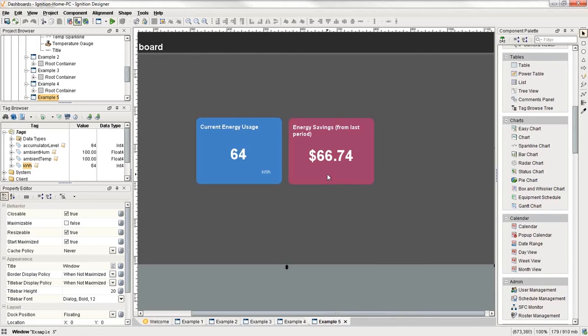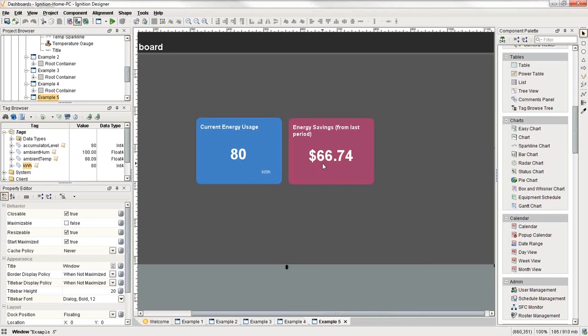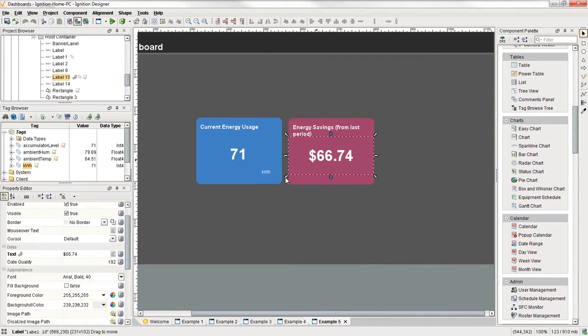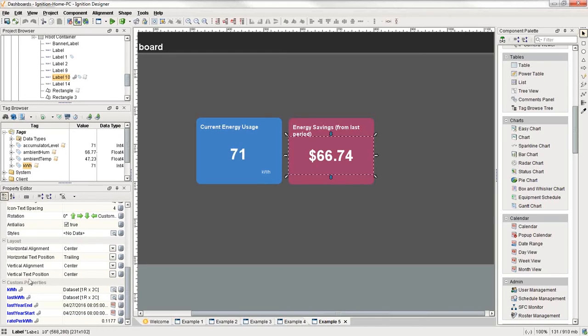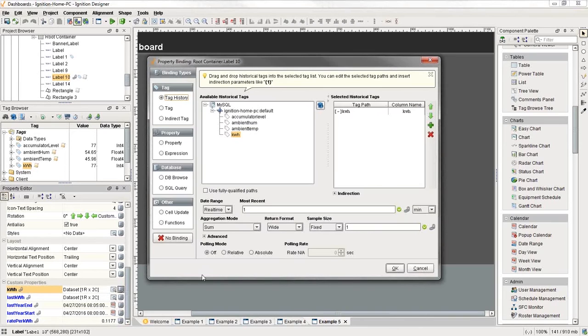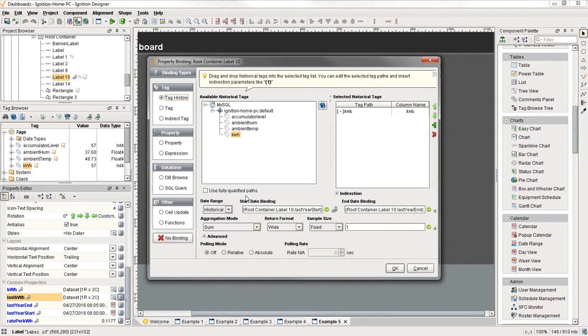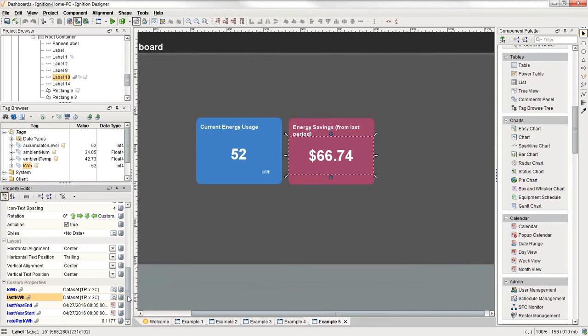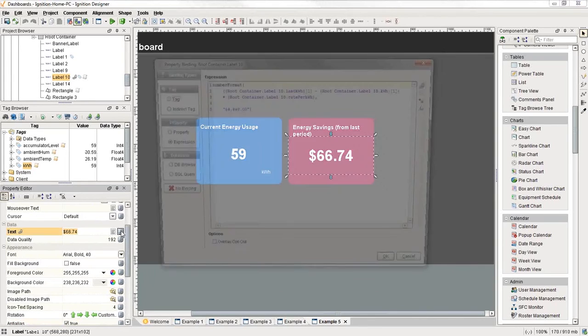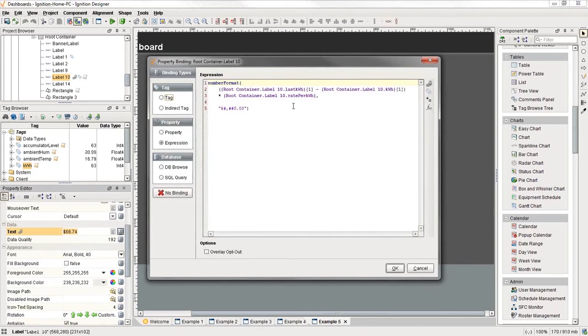Secondly, we have to know what it costs per kilowatt hour and this information is going to exist in different sources. So the historian might have the data for the information of the actual current energy usage. But another outside tool like a web service may have information for the actual dollar per kilowatt hour amount. And so it's important that we can then, in here, you see down here at the bottom left I have some properties. The idea is I can actually go get the information for the current through the historian and through the same period last year in the historian, and then I can go off and do a call to web service to get the rate per kilowatt hour.